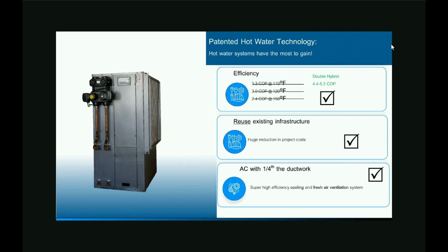Remember, we get 80% of our heat out of the baseboards and radiators that are already in place, and we can fill the hole, that 20% gap, with the forced air. And then we can get air conditioning. We can put some ductwork into the building, not replacing all of it with forced air, but just a little bit of ductwork, about a quarter as much as you would typically use, about 100 CFM per ton, and we can use that to provide supplemental heat.